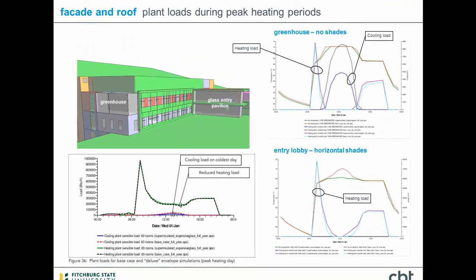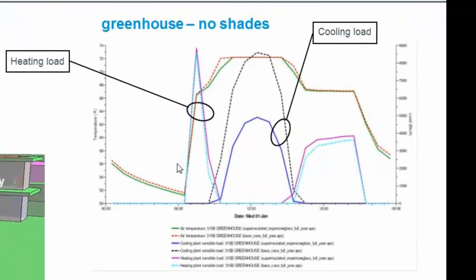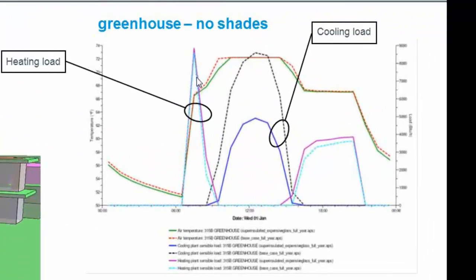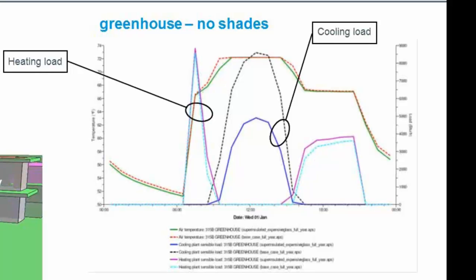So I was able to go through room by room and in real time watch these graphs update room by room to see where the loads were. Identified that we have a southeast facing greenhouse. It's not really a greenhouse proper, but more of a botanical sciences laboratory. But it's southeast facing, very tall glass with no shading. And it was, as you see here, these lines indicate the heating loads early in the day. And then as the heat gain comes in, we actually got into a situation where they had a demand for cooling, and then later in the day, switched back over to a heating load.